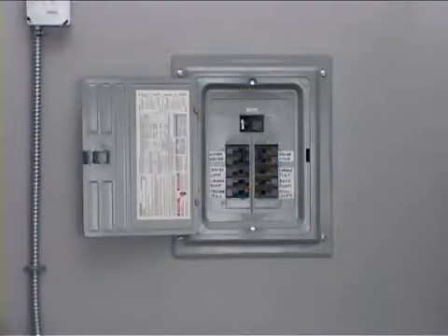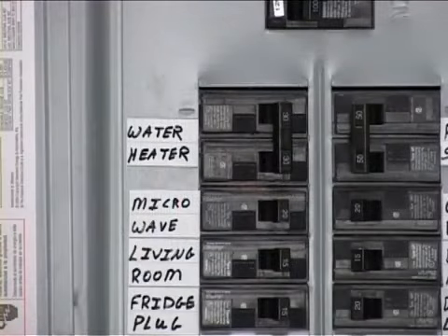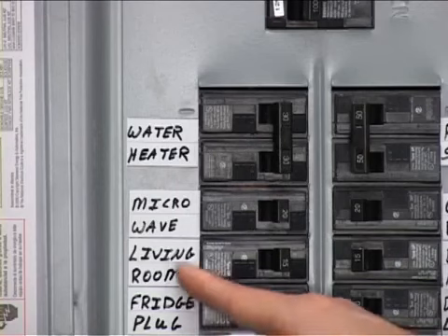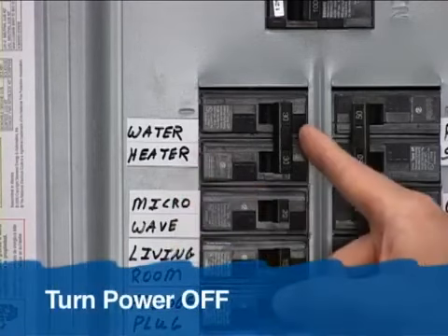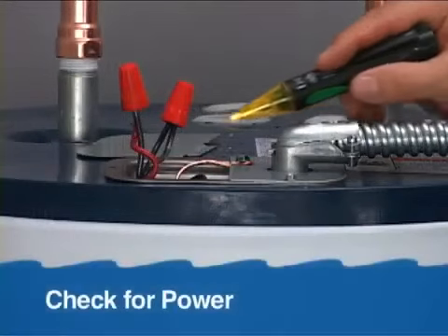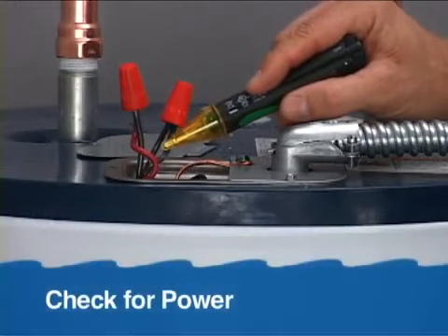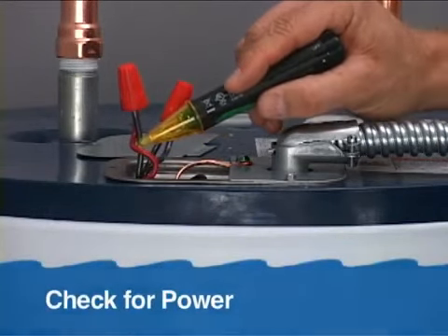Before removing the old water heater, make sure electrical power is off. Locate the circuit breaker marked water heater in the main electrical panel and turn it off. Because electrical panels can be mismarked, also check the circuit for power with a circuit tester or meter.